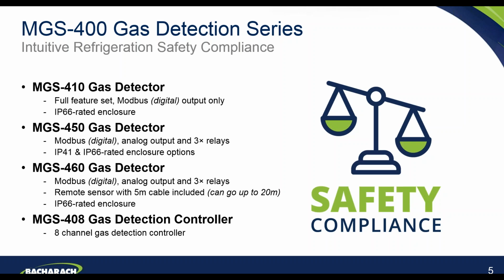They want to have purely a Modbus output that connects and interfaces into their control system, and then that control system drives all of the other actions associated with alarms and faults and data logging, etc. The next variant is the MGS-450 version of the gas detector. This has Modbus, but it also incorporates analog output and 3 relays for your alarm notification and fault notification. The MGS-450 is available as IP41 or IP66 rated enclosure versions. So again, you can choose those depending on the application and project requirements.